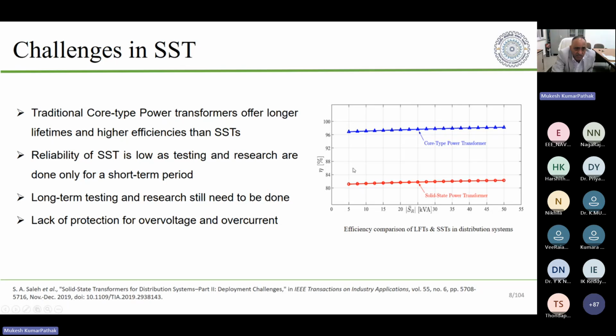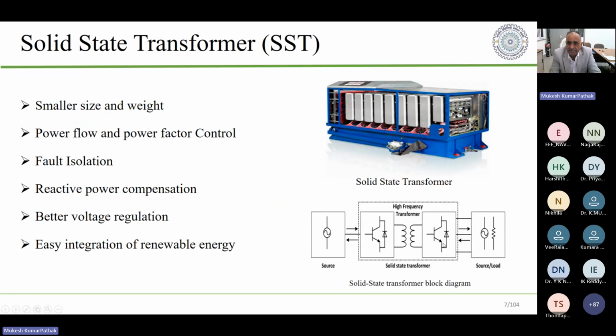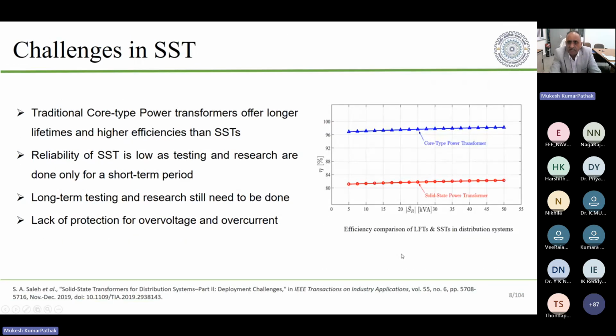So core type transformer efficiency is one thing. Then the traditional core type transformer also offers longer life. This transformer is highly inexpensive and a very simple system. There are windings, there is a core, you don't have much more than that. Because it's simple, it will have longer life. Whereas in the solid state transformer, as we can see in this slide, we are creating a lot of power electronic systems. This will make its reliability low, and it is still under the research stage. Large scale adoption is not yet there. So we need long-term testing and research to make this transformer viable for real world applications.